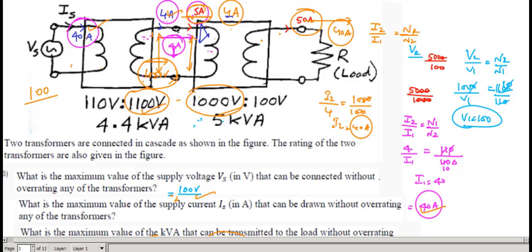I am applying the transformation ratio to the secondary of the second transformer, which is connected in cascade to the primary transformer, and getting 40 amperes. V2 here is 1000 volts, since it only requires 1000 volts, and correspondingly V1 is 100 volts.